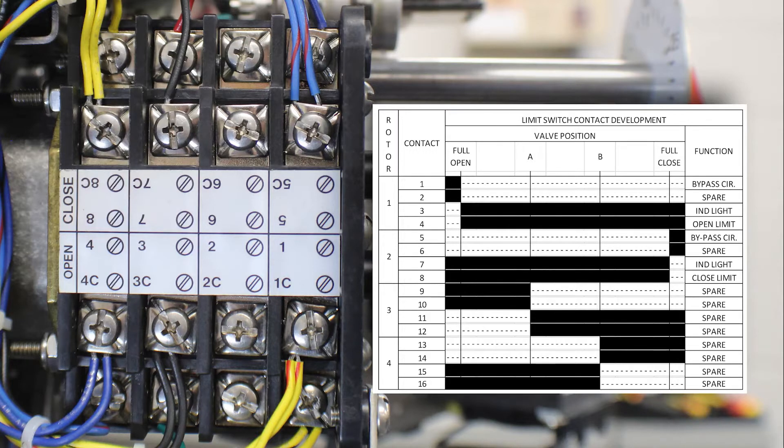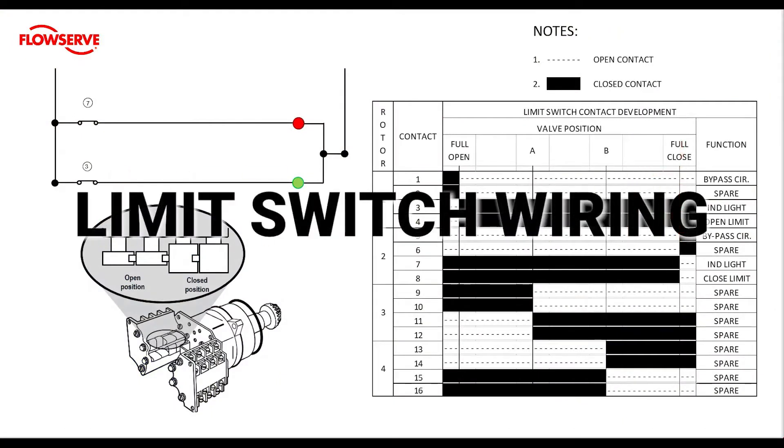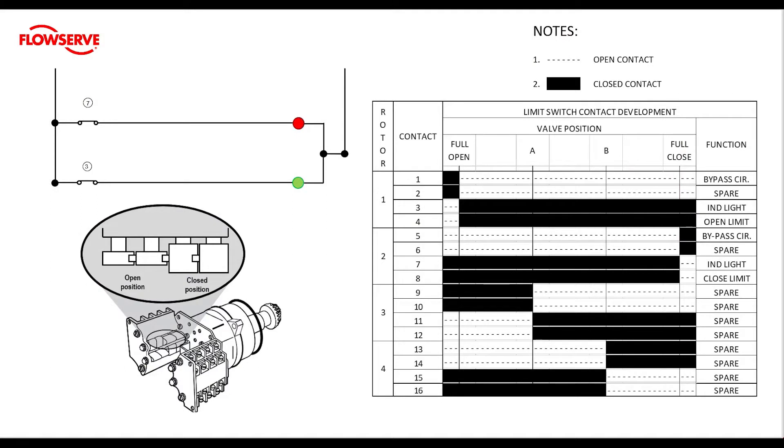Let's take a look at part of the wiring diagram so that we can understand how to set the limit before we pull it into practice. We are going to zoom in on two parts of this drawing: the lights driven by the limit switch and the limit switch contact development chart. On the lower left hand side of the screen there is a drawing of a limit switch and a diagram depicting what an open contact looks like versus a closed contact. This diagram's point of view is from the top of the limit switch looking down. In the upper right hand part of the side, we'll see a legend showing how to read the limit switch contact development chart. A dashed line indicates an open contact and a solid block indicates a closed contact.